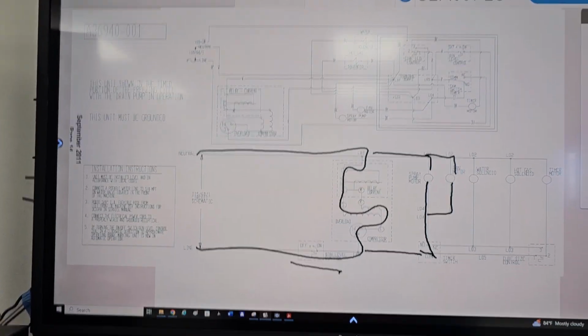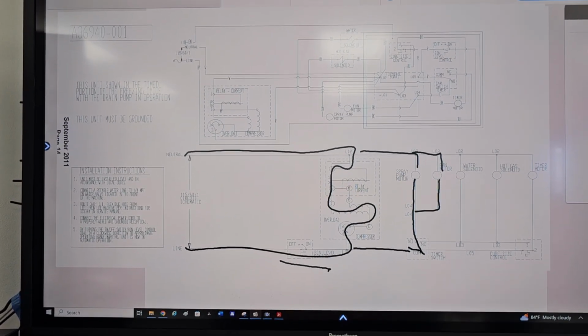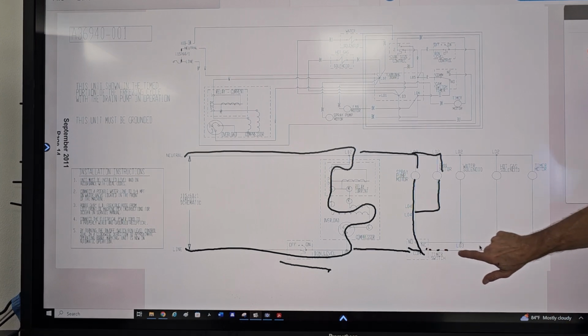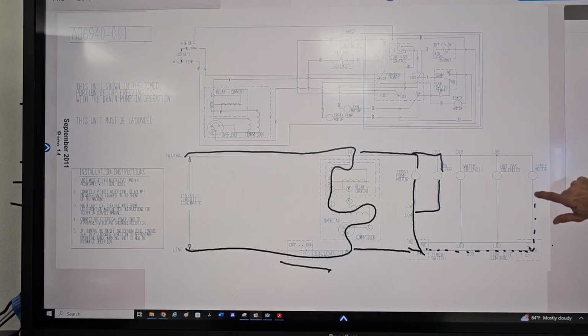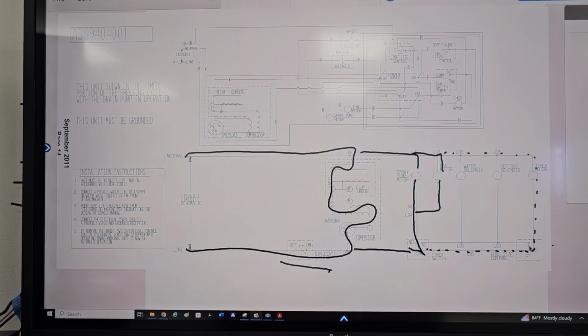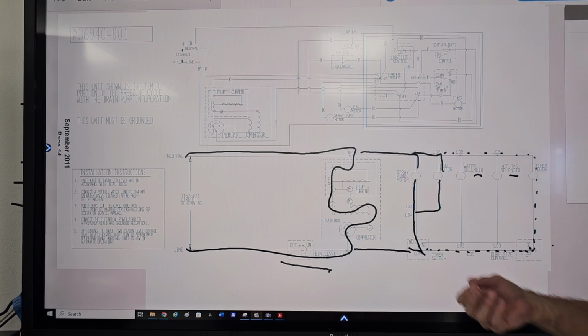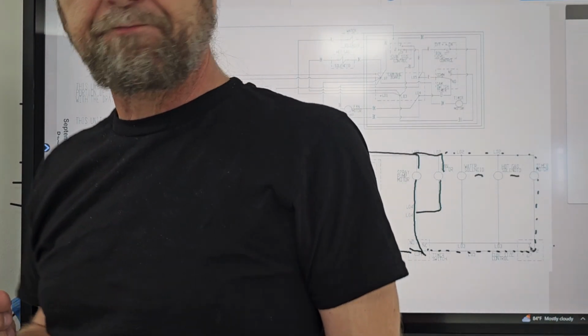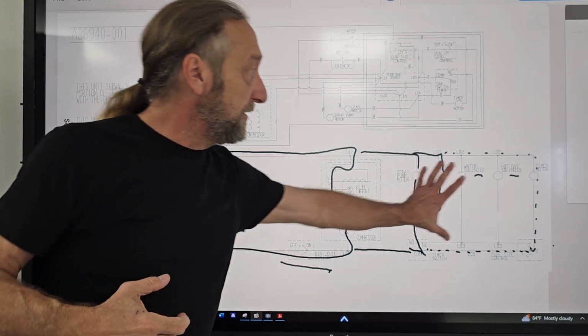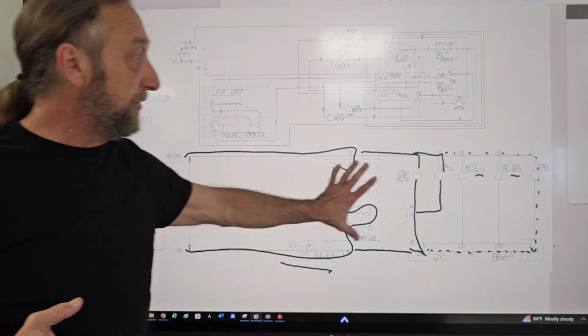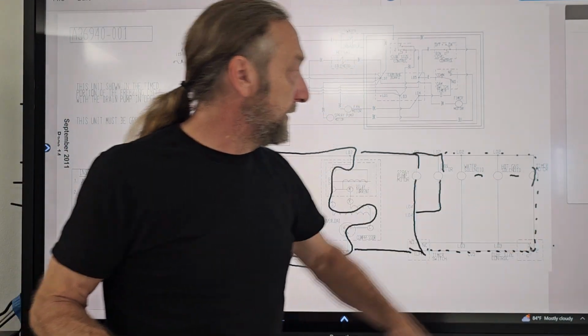So let's go back to the schematic here. While it's running, the other thing is the timer motor. So the timer motor is running. Now, as it's running, the hot gas solenoid and the water solenoid, those two components are working. I'll explain to you what the hot gas is in a minute. But these are the only three parts that are working besides the timer motor, that's it.